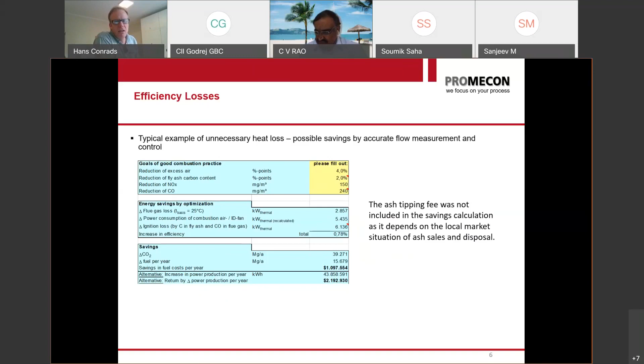The values that I look at are the following. I look at the coal feed, I look at the air feed, and I look at the delta temperature. Why am I doing that? If you have the same coal going to the mills, then the enthalpy loss of the air per ton of coal should be the same on every mill. Because most of the enthalpy loss comes from the evaporation of moisture, right?